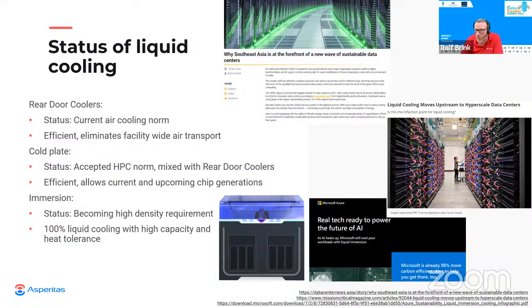Immersion is also known from HPC applications and is now breaking through to become mainstream strategy for HPC and high-density platforms. The biggest value of immersion lies in the holistic, all-encompassing cooling approach. Since the IT equipment is fully immersed, 100% of the converted energy is captured in a dielectric liquid, and this full cooling ability is therefore the most important contributor to addressing efficiency and sustainability goals.